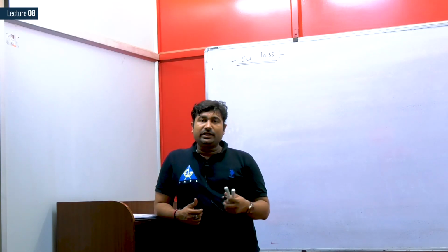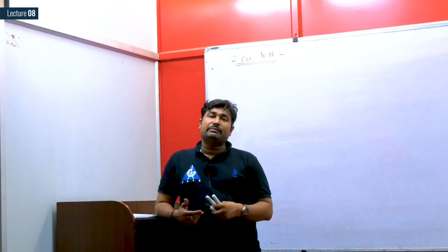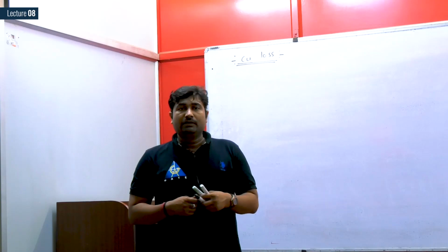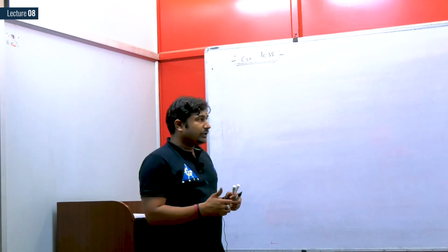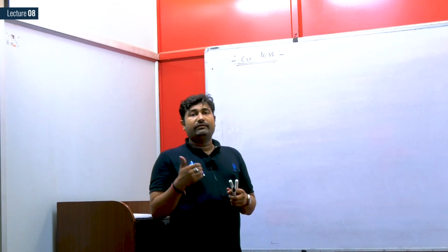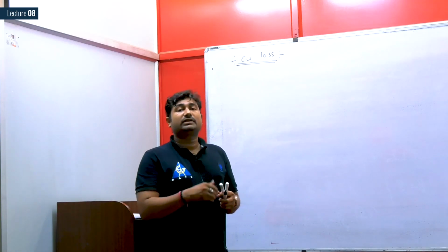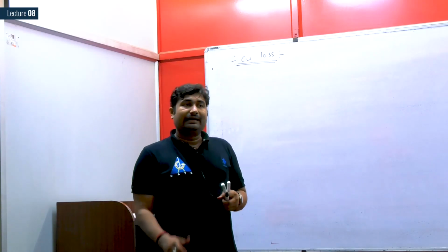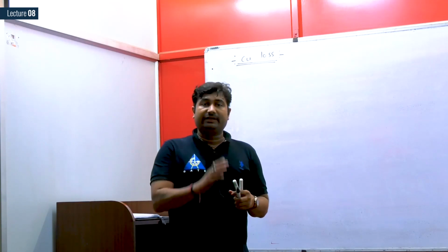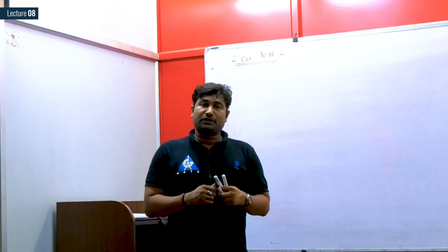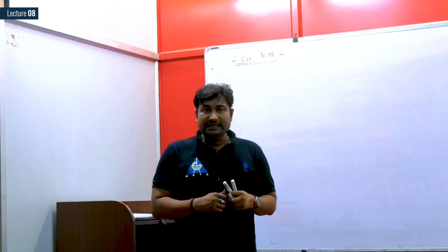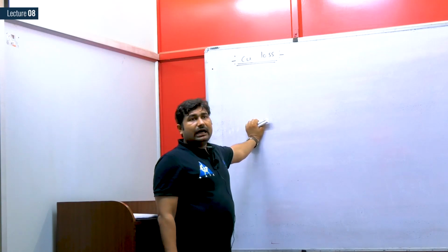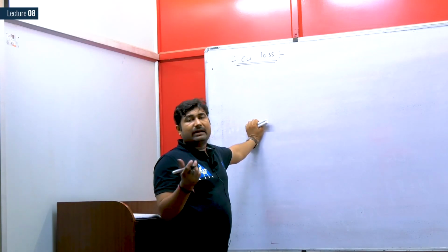Okay. So in case we know the temperature rise or the operating temperature of the transformer, then we can calculate the operating copper loss in a more accurate format. But presently we are just in the introduction phase of the transformer. So we take R, that is the resistance of the wire used in the transformer, as a constant parameter, and that resistance is considered to be at 75 degrees centigrade because the standard operating temperature of electrical machines is 75 degrees centigrade. So these losses should be calculated at 75 degrees centigrade for mentioning the parameters on the nameplate.